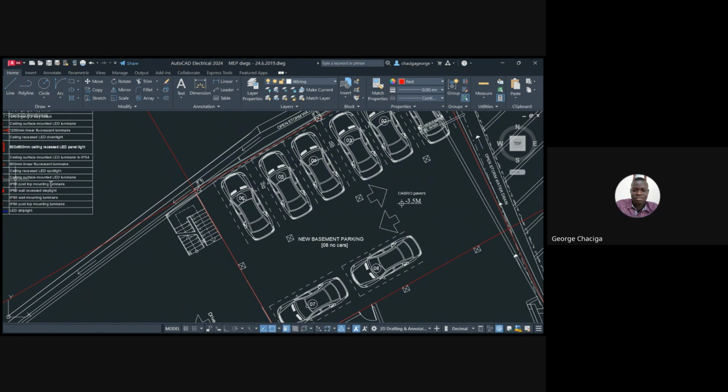lighting points. Because if you have 4 lighting points, of course the separation will be a bit less than what? The 4.5 meters that we target. Because if you bring this back and you divide by the 4 units that we decided, you see that the distance becomes smaller. But that is better because we're still in range.